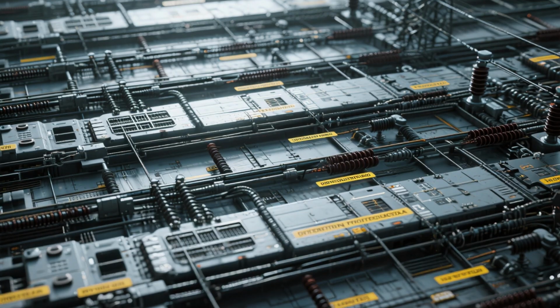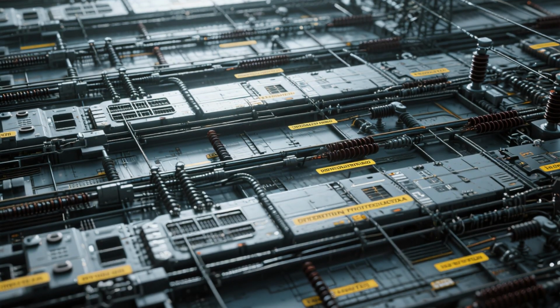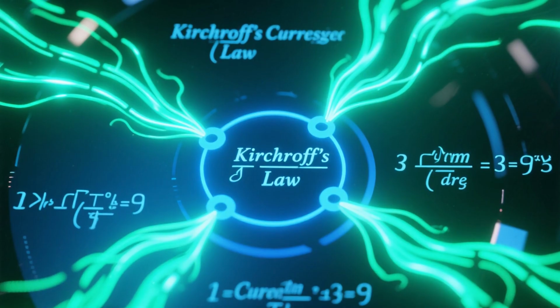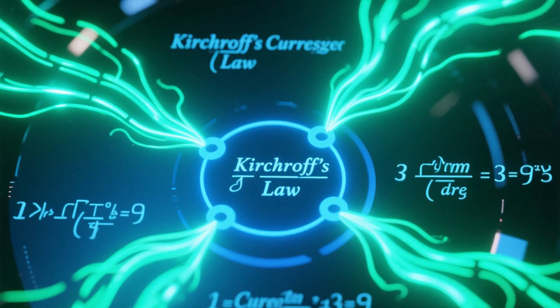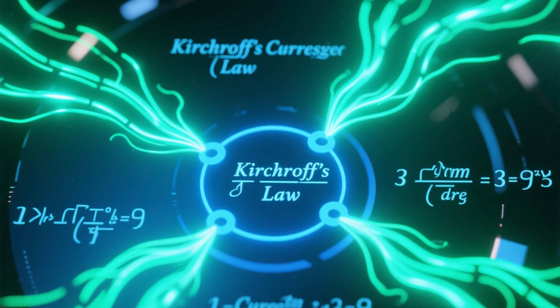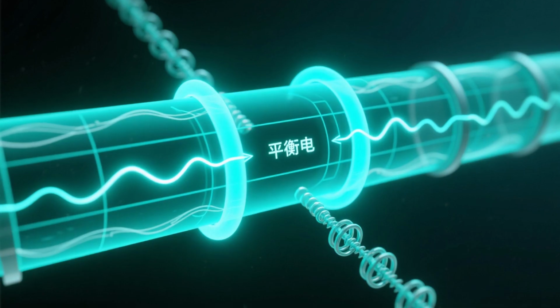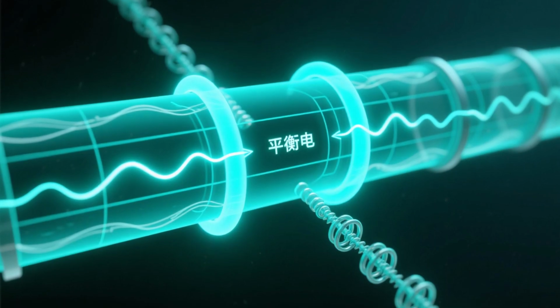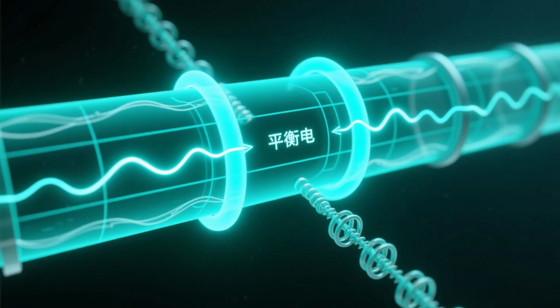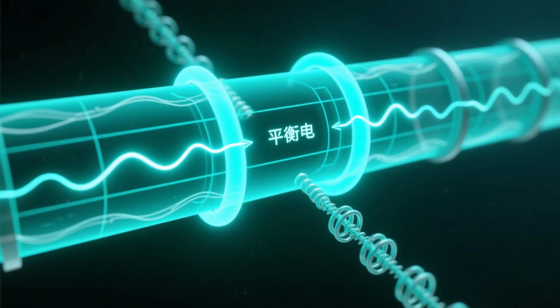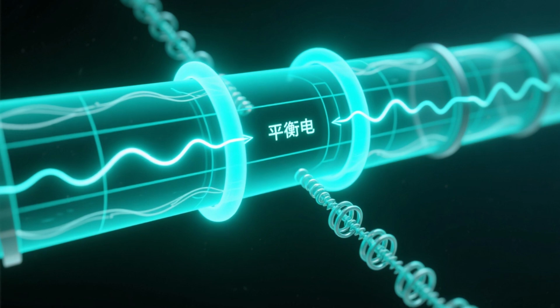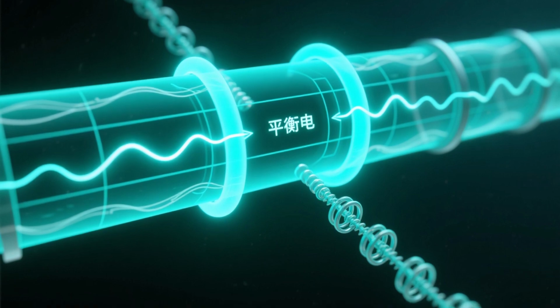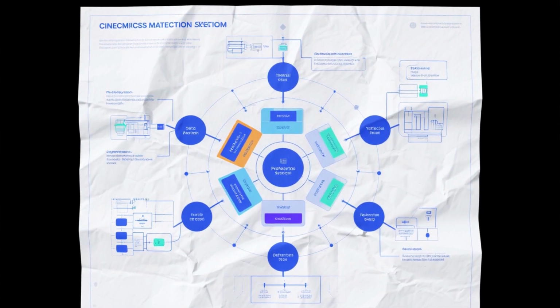Another robust backup protection method is differential protection. This technique is based on a fundamental law of physics, Kirchhoff's current law, which states that the sum of currents entering a node must equal the sum of currents leaving it. In the context of a transmission line, this means that under normal conditions, the current flowing into one end of the line segment should be exactly equal to the current flowing out of the other end. The differential protection scheme leverages this principle with remarkable effectiveness.